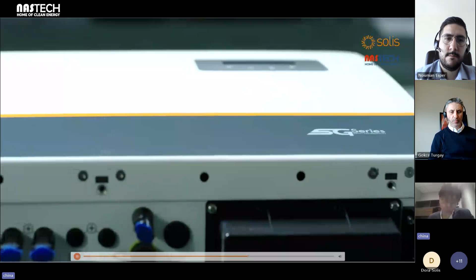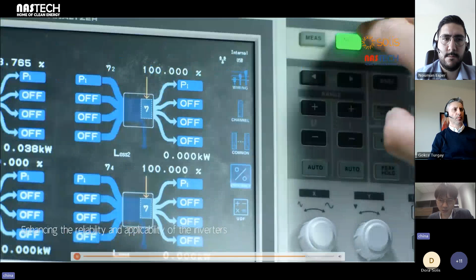What I'd love to mention here is that we are using air to do the sealing test, which is more strict. Some other manufacturers simply use water. With air, the test condition is much more strict, and with that we can guarantee our IP level is more stable. Also here, we are doing some functional and electronic tests. We can see a lot of data on the different simulations, just to see that our inverter works in proper condition.